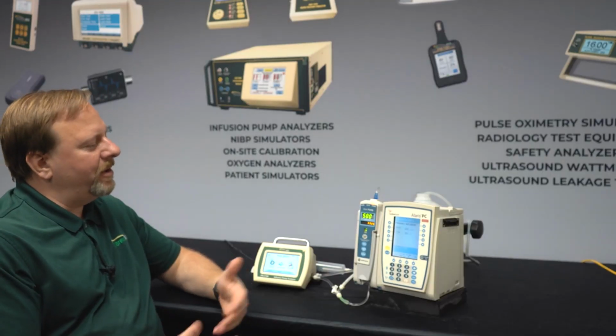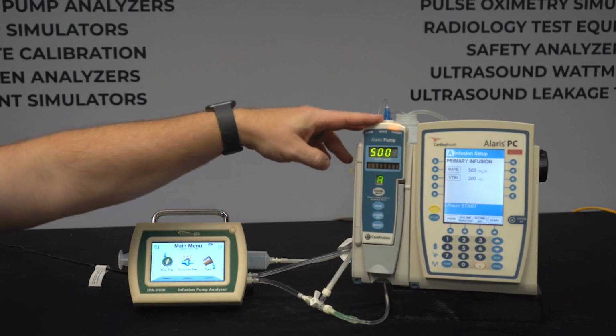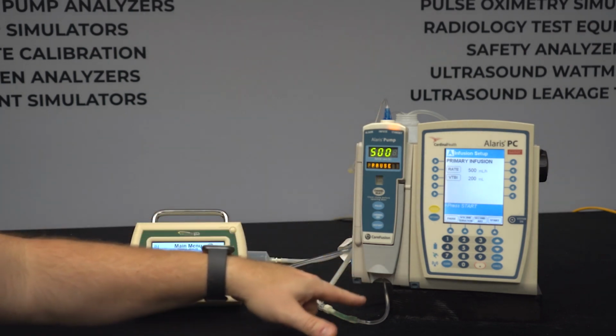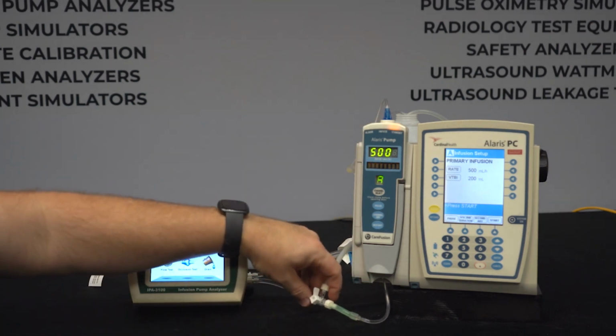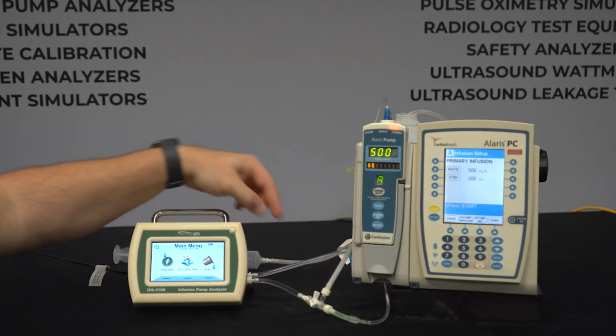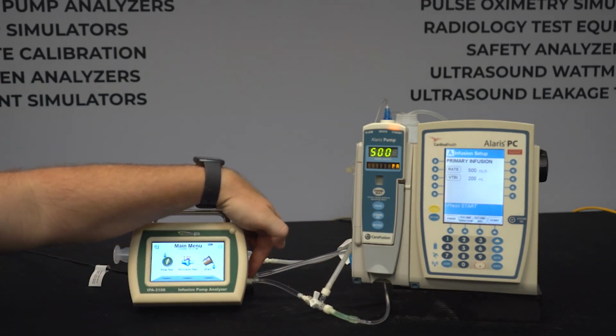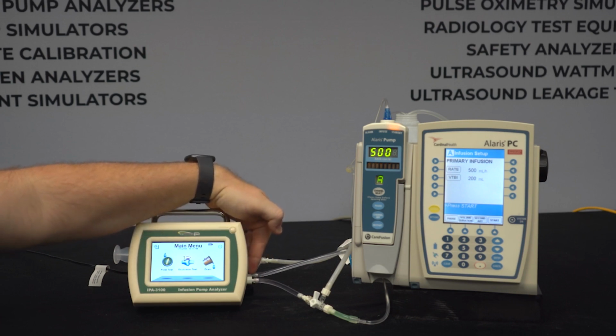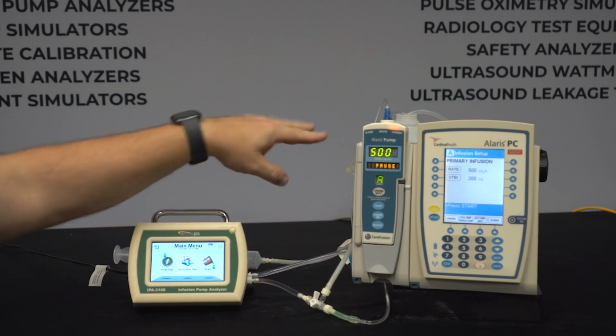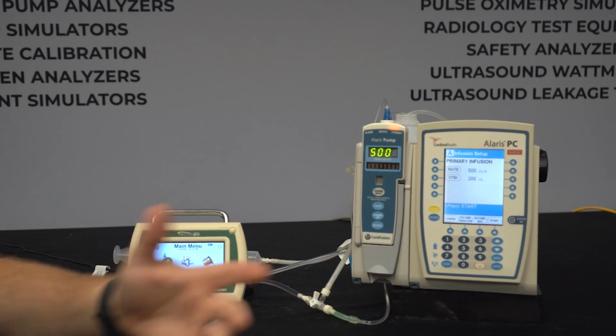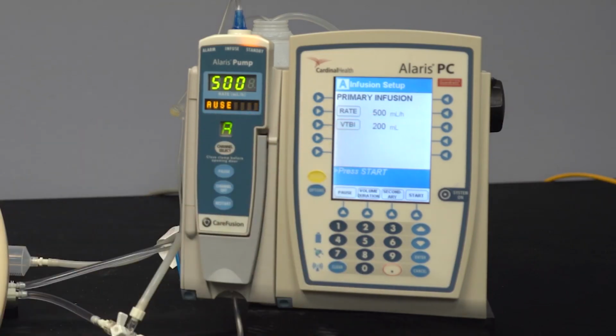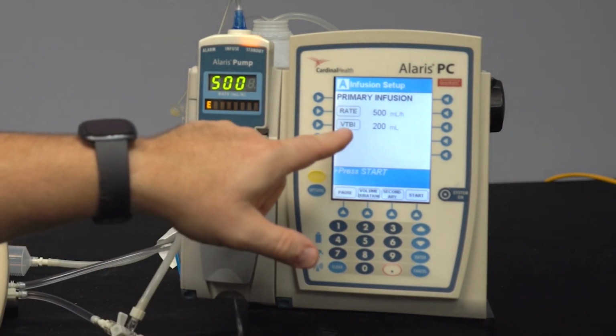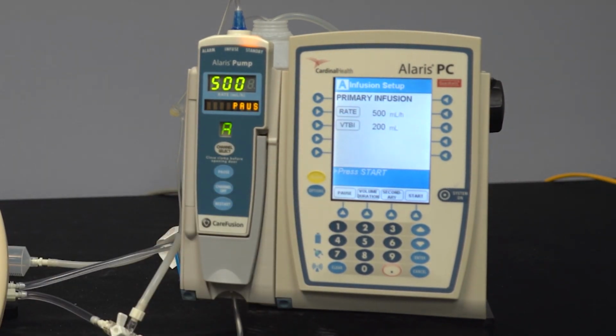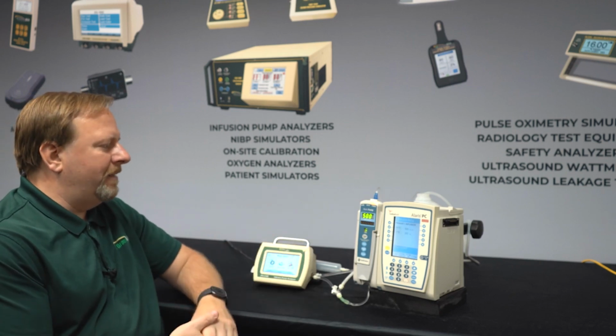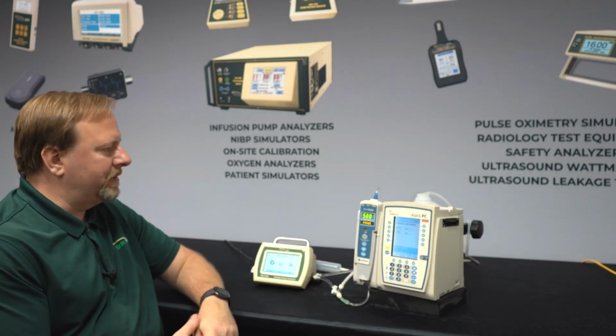Okay, so if we take a look at our configuration here, we've got an Alaris infusion pump. We've got that connected to a T where I can inject a bubble. And out of the T goes to the IPA 3100, and then the outlet of the IPA 3100 goes back to our tank where we have our water. I've got the infusion pump set for 500 milliliters per hour just to make it go a little faster. And I've got 200 milliliters set for dispense. Again, the rates don't matter. This is just for demonstration purposes.